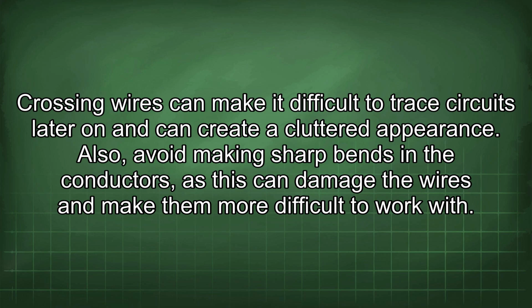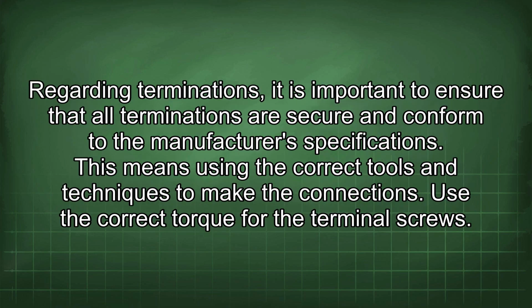Also, avoid making sharp bends in the conductors, as this can damage the wires and make them more difficult to work with. Regarding terminations, it is important to ensure that all terminations are secure and conform to the manufacturer's specifications. This means using the correct tools and techniques to make the connections. Use the correct torque for the terminal screws.